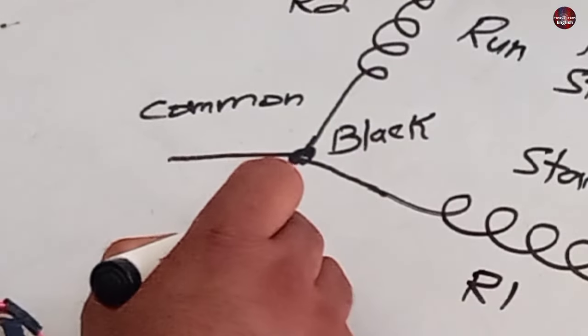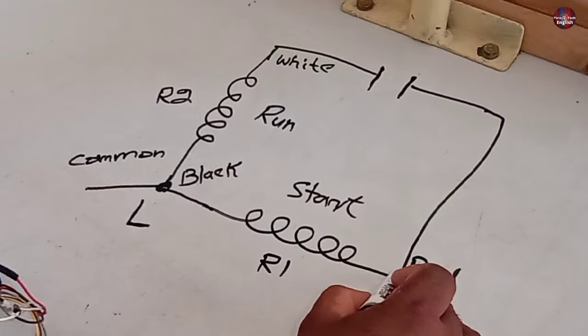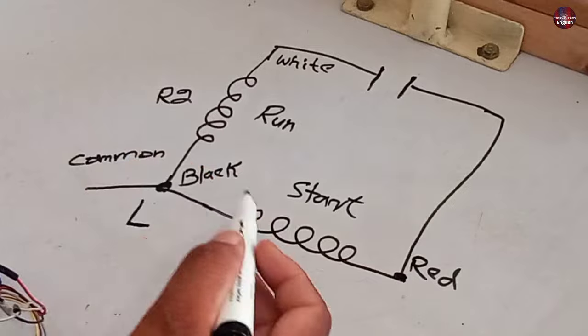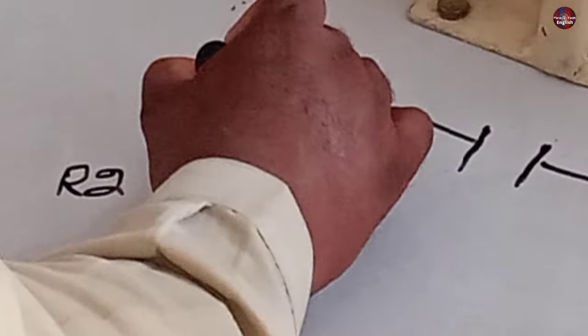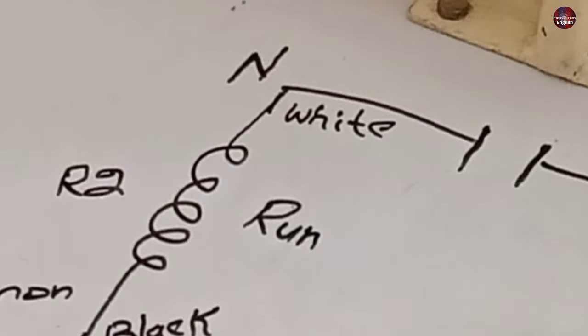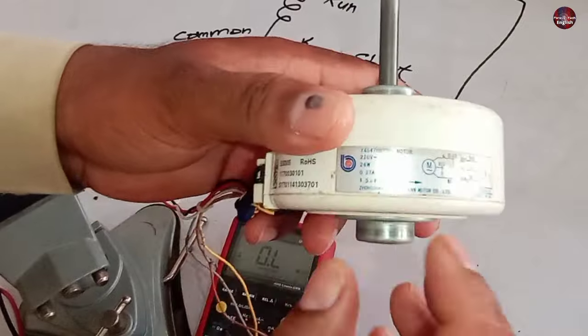Always remember that the common wire is always given the phase or line connection. Now I will erase it and install a capacitor with white and red wires. We know that the run is the white wire and the start is the red wire. The neutral wire will be installed with the white or run wire. And the red is joined with the capacitor. And this is how to do the wiring of this motor.